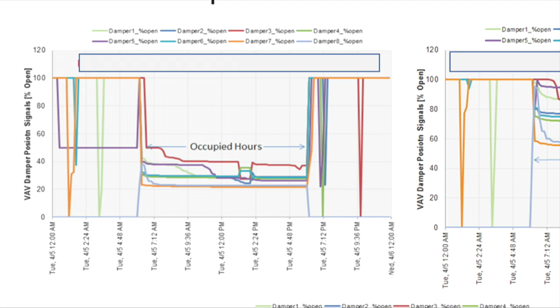So, yep, that operation has damper positions all under 50%. That's exactly right, Robert. Your system is running highly throttled -- everyone's got more than enough temperature, so the VAVs are throttling, and that means you're driving the system with too much static pressure. You can get by with less static pressure.